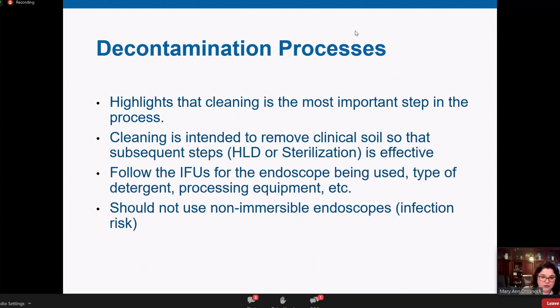So we need to follow all the steps of processing, follow the IFUs for the endoscope, adding in these best practices and quality parameters outlined in ST91 for all steps along the process. We clearly point out that if you have endoscopes so old that they cannot be submerged for a leak test, because they were never engineered that way, they should absolutely not be used, because that's an infection control risk - we can't tell whether those scopes are resistant to water and fluid invasion or not. Definitely don't want to use those scopes anymore. Unfortunately, I do see that once in a while when auditing facilities, that they're still using scopes that old, discontinued for many years and not supported by the manufacturer or other repair companies.